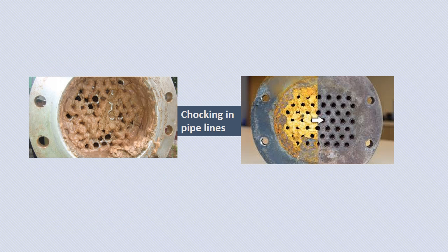See the view of the choking of the pipeline here. In both the figures, you can see how the precipitate starts choking the pipeline and disturbs the working of it. So pressure automatically increases. So we have to reduce the fuel level so that the pressure is maintained properly. Otherwise, it creates a lot of problems in the industry.